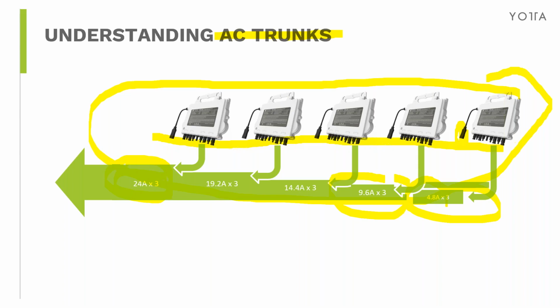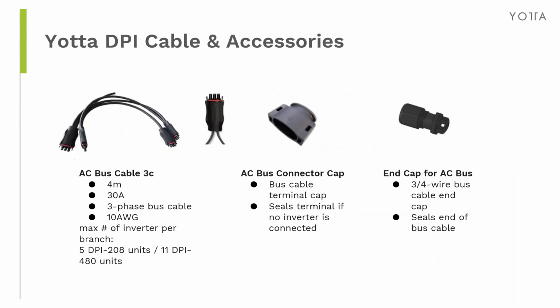So it's cumulative. If we were looking at, let's say, a 480 volt system, you're looking at 11 inverters, up to 44 modules, again on that 10 gauge trunk cable, all the way down to a three pole single throw breaker. As far as accessories are concerned, very limited, very minimal. The AC bus cable or trunk cable is a 3 conductor, with 4 meters between drops. It can be used up to a 30 amp, so that's where we get the 30 amp 3-pole breaker. And as I mentioned, 5 units on the DPI 208 and 11 units for the 480.